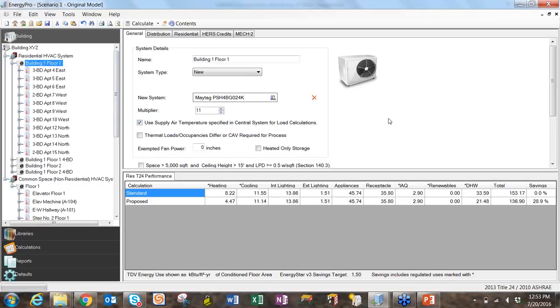Okay. Yeah, and on the same note, I'll give you an example. I'm working with an energy consultant where they're proposing to install heat pumps for space conditioning and domestic hot water purposes. And it's a high-rise building, around 23 or 25 floors. But when they put their system in the model, they're getting a heavy penalty. The reason is your standard system is a chilled water system, and our chillers in part load conditions operate way more efficiently than any other system available in the market. So that's a drawback. That's why we are proposing that you change the occupancy to multifamily.